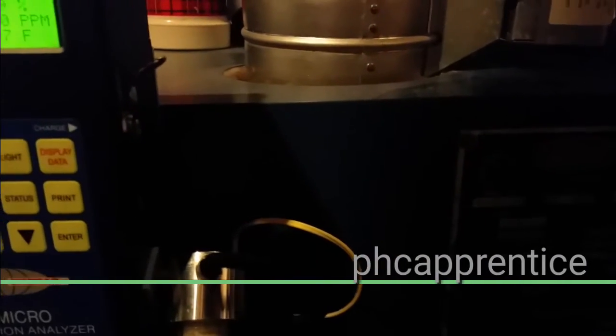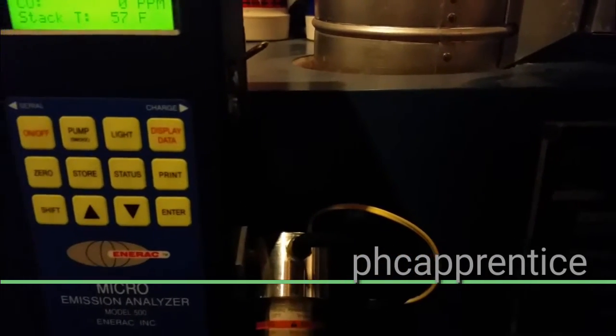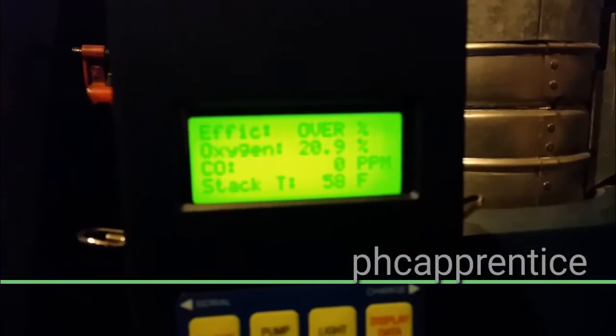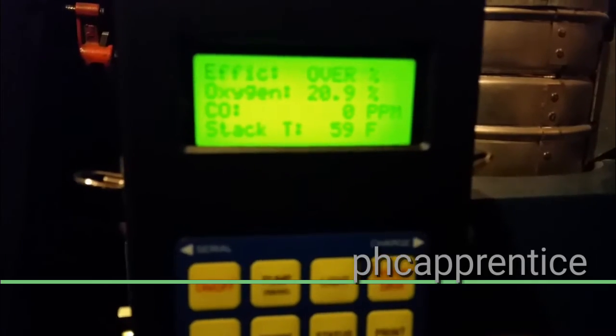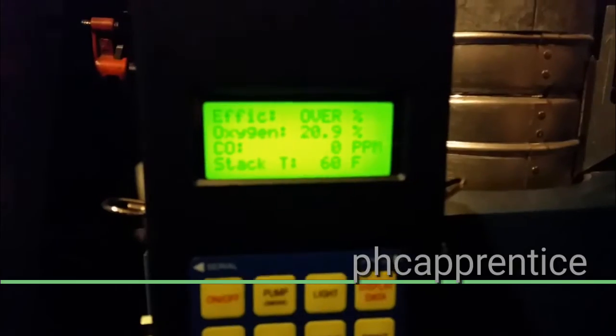Now I've got a 20,000 parts per million sensor in here, so the boiler is cycling, the flue damper is going to close and reopen, and I'm going to go ahead and take a reading with the probe assembly, which looks like this. Put this right inside the breech, and I'm going to go from there. Since this is a 20,000 parts per million sensor, I'm not worried on startup. But let's see what the CO is. I have a reading from a couple weeks ago on my old Bacharach.